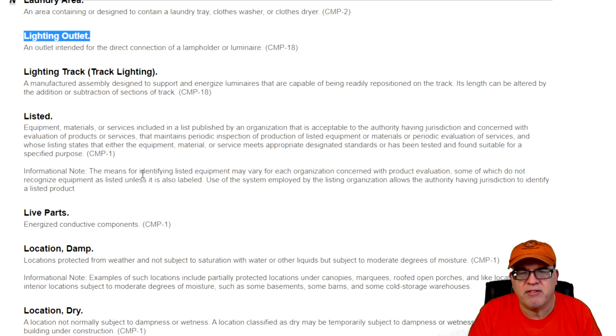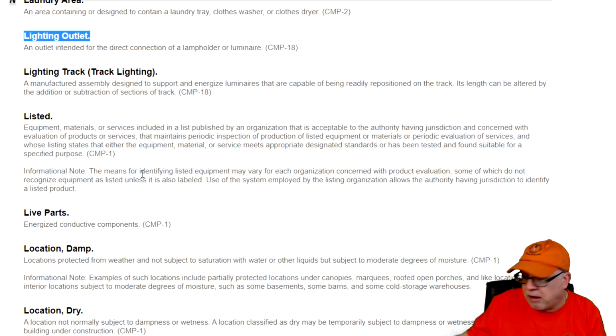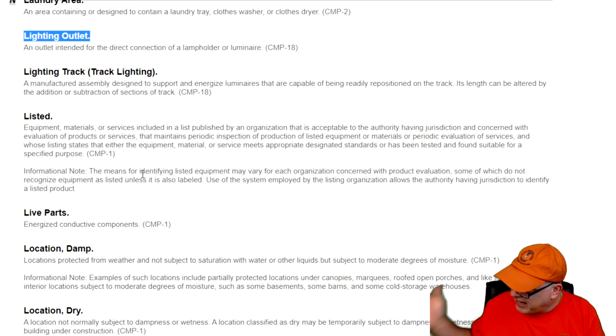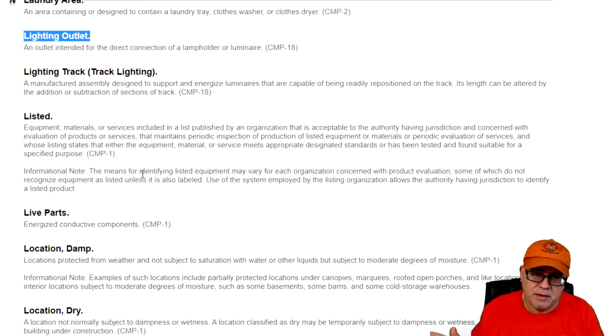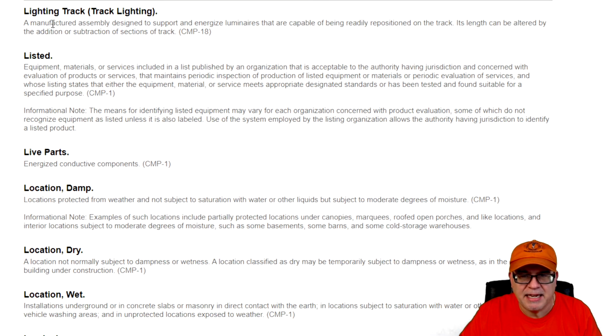Okay, so when we see something like outlet in the code, don't think receptacle, because we're so used to saying, hey, look, you got an outlet right there. Yes, it's a device that is in an outlet box, and you could refer to that box as a receptacle outlet. Okay, but the actual device that goes in it is a receptacle, okay? You get my point. Track lighting, okay?